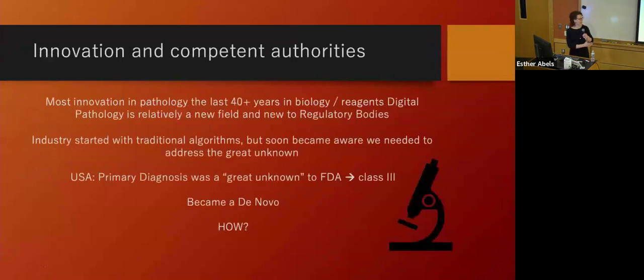So what happened with digital pathology? As I mentioned, before you go into AI, you need to look at what's already there. For the FDA, jumping straight away to AI was a big leap, because the acquisition device is the input to the AI. So we need to make sure that device is functioning properly, and also that when you review it on a screen, the pixels are displayed correctly. If you set two screens next to each other, you always have a different image. So are you still comfortable making the diagnosis?